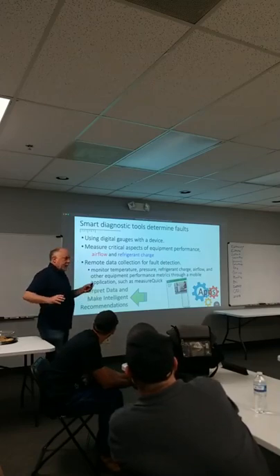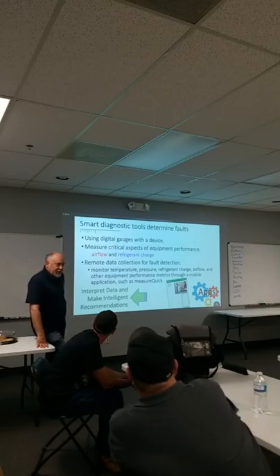The biggest things we want to talk about, and I was on the phone with a guy today, he's like, well, wait a minute, I'm really curious, how much longer does this take to commission a system? And my question is, well, how are you commissioning the system now? Because if you're just flipping on a switch and making sure it blows cold air, it's definitely gonna take you a few more minutes. But there's really only a couple things we can adjust in the system, which is what? 2 things we can adjust. Charge and airflow. Charge and airflow, right? So if you're gonna commission a system, we're pretty much just verifying a proper installation, verifying proper piping, pipe pitch, oil return.